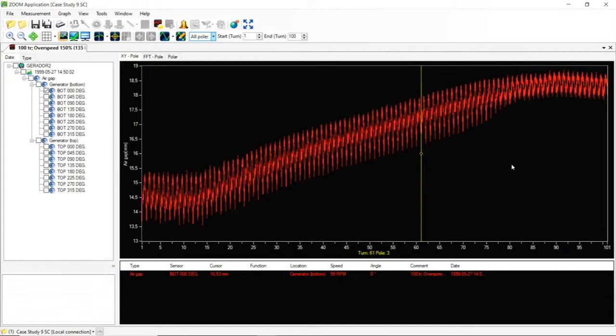So everybody was giving high fives, everybody was happy. But then I told them, well, it was supposed to do it here, but it was supposed to do it here. In reality, it starts doing it about here, which is about 86 RPM—that's below nominal speed. So the utility engineers said, well, that's totally unacceptable. If that's the case, it means theoretically the rim could start floating at any time in operation at full load.